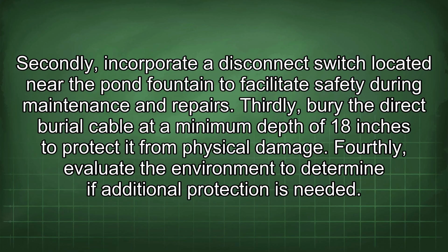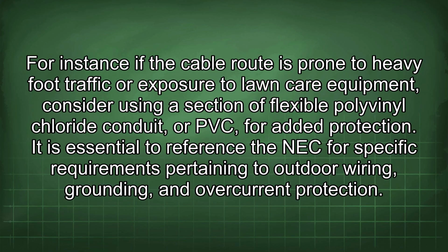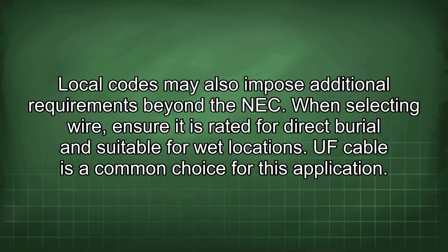Fourthly, evaluate the environment to determine if additional protection is needed. For instance, if the cable route is prone to heavy foot traffic or exposure to lawn care equipment, consider using a section of flexible polyvinyl chloride conduit, or PVC, for added protection. It is essential to reference the NEC for specific requirements pertaining to outdoor wiring, grounding, and overcurrent protection. Local codes may also impose additional requirements beyond the NEC.